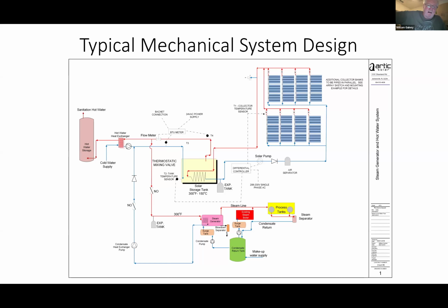Solar thermal systems are pretty simple designs. Somebody asked me once, what's the difference between a residential solar water heating system and a commercial solar water heating system? And I said, it's basically just bigger. Solar thermal is proportional, so the savings are proportional. Whether you do an 8-hour day or a 24/7 operation, it's always proportional, which is a good thing for us because it's easy to calculate. So we have the solar collectors heating our storage tanks and then going into our process heating, whether we're doing process heating for a manufacturing facility, or process heating for sanitation at a meat processing or a dairy operation.